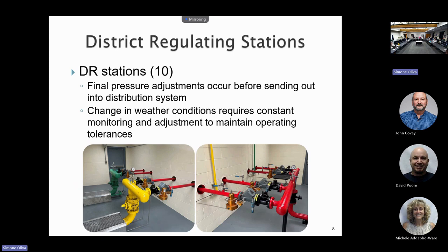Our technicians luckily all live very close, within a 10 or 12-minute ride, including myself. We get a call from the control room and usually can have somebody on site within 20 minutes to look at our SCADA system and identify the issue. Our low pressure system is all tied together, so it might not be the one that's alarming that needs adjustment, it might be another one in the system that's more reactive to what the system does.